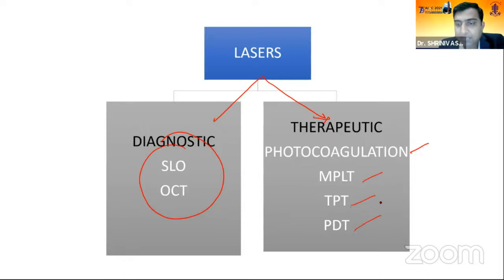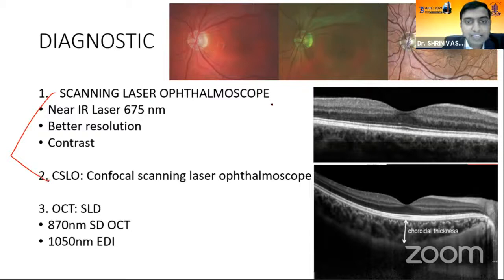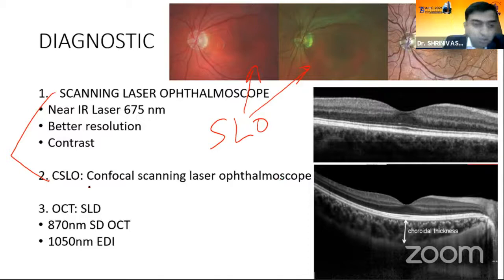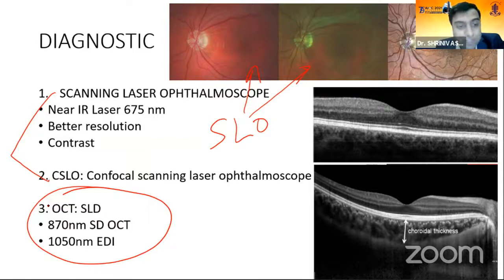In diagnostics, we have two types. The scanning laser ophthalmoscope (SLO) is used for capturing fundus images, and the confocal scanning laser is used in Heidelberg technology for multimodal imaging. In OCT, we have evolved into spectral domain and now Fourier domain, using 870 nm and EDI with 1050 nm wavelength to better analyze choroidal tissues.